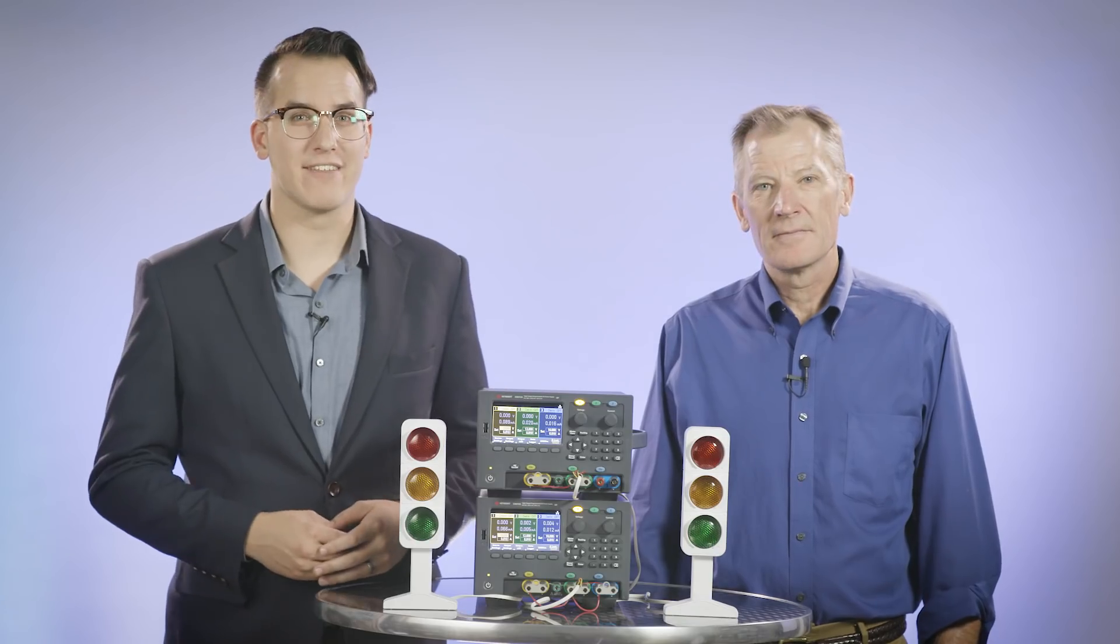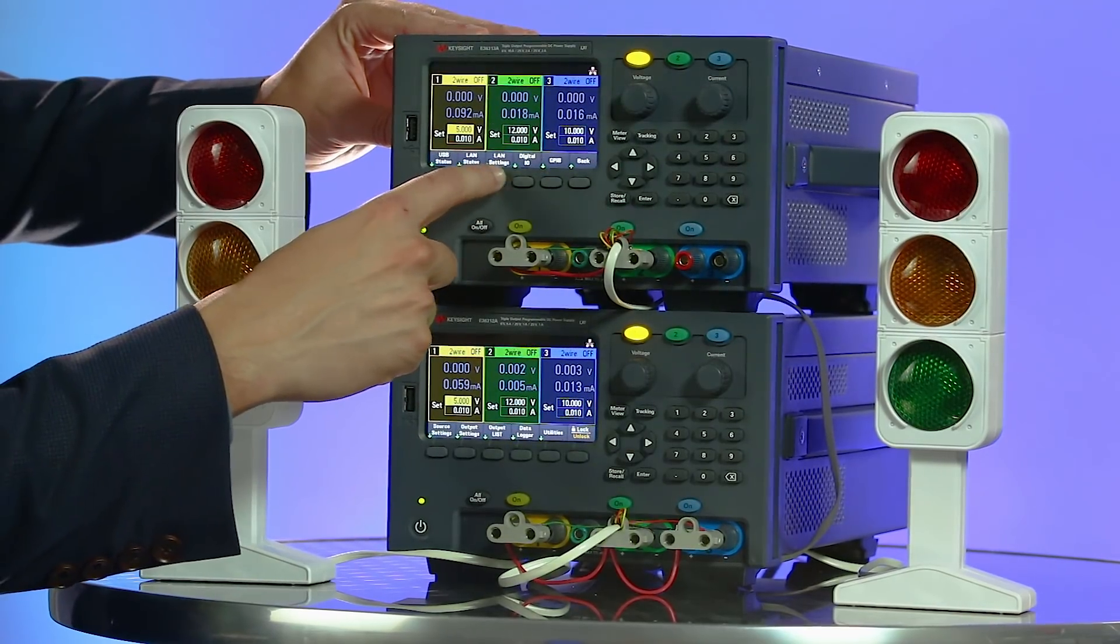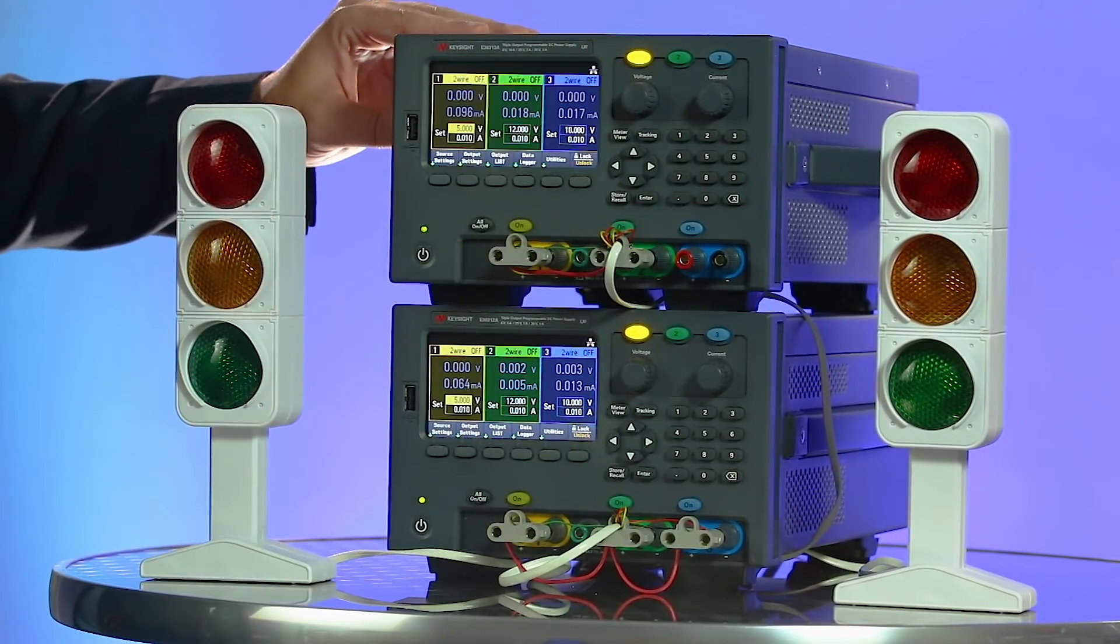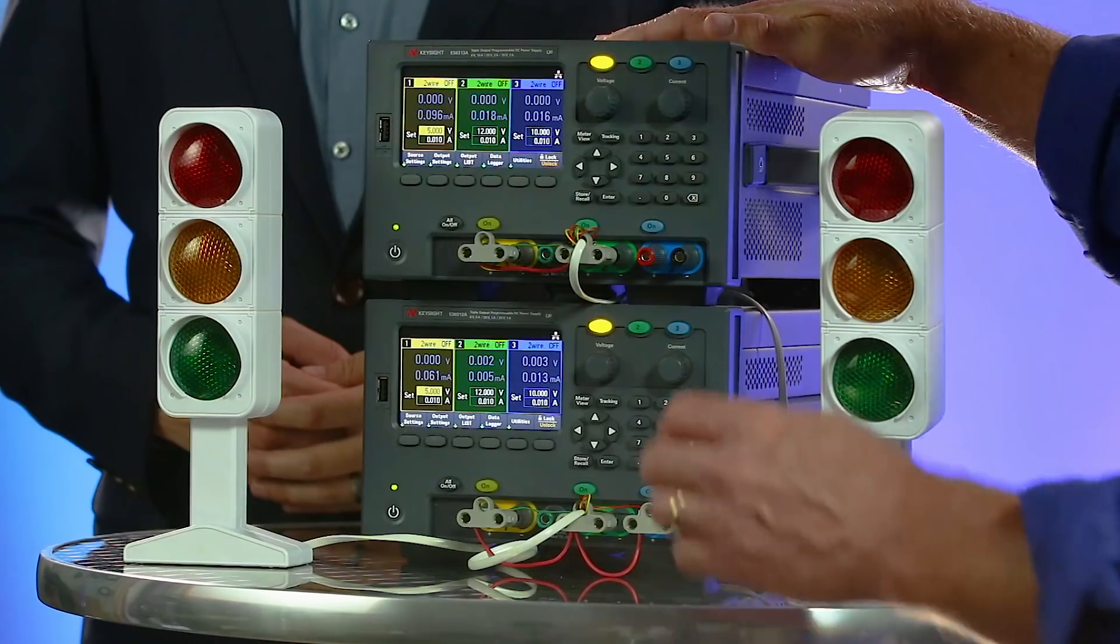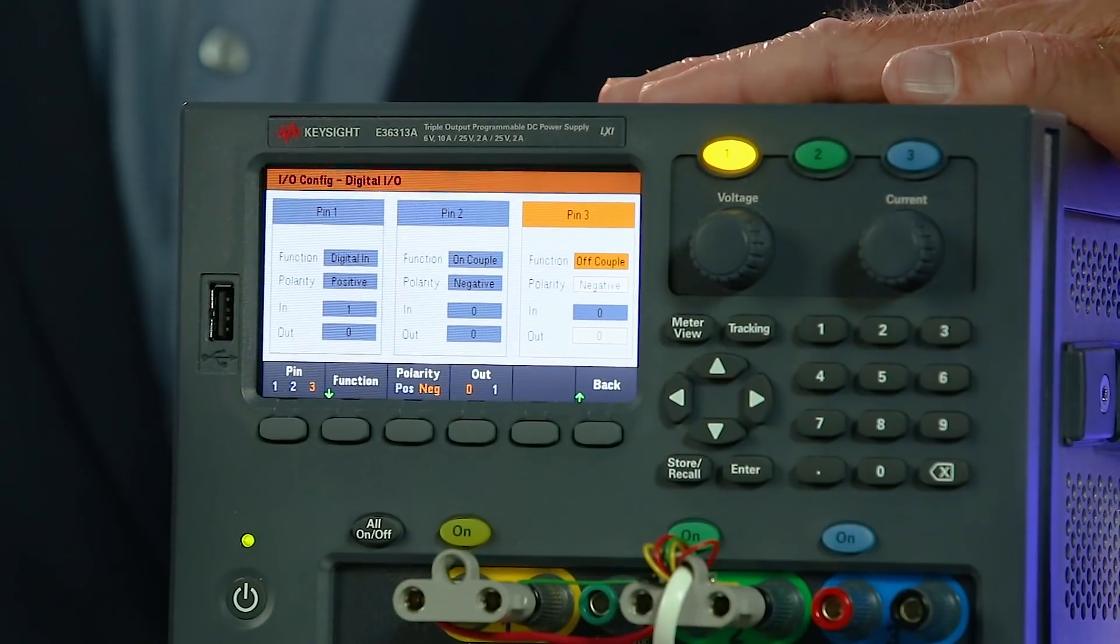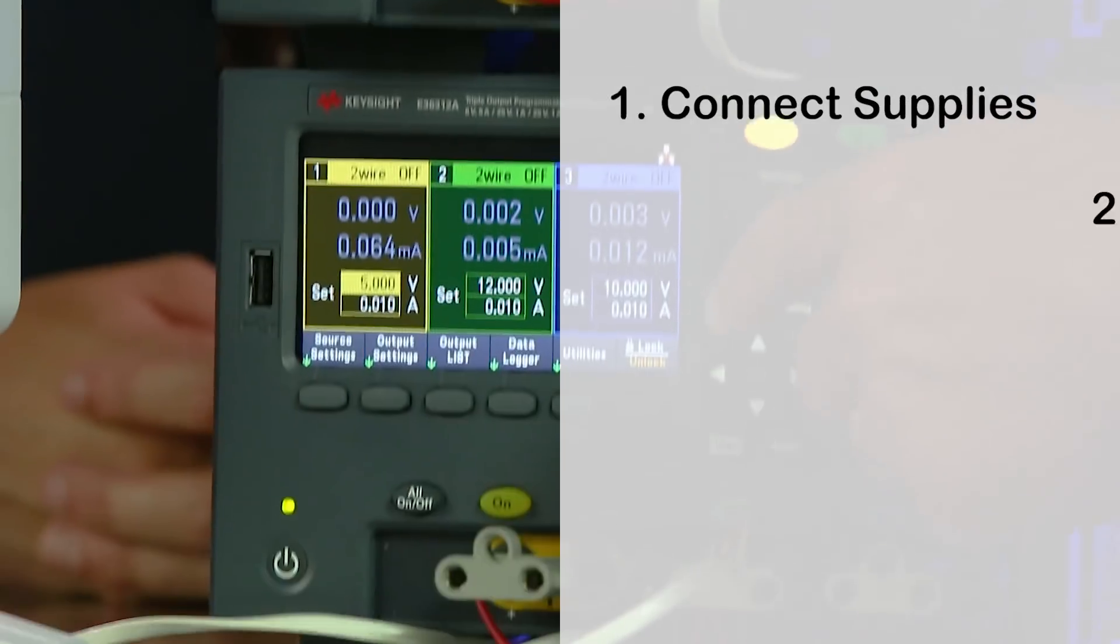A quick fun UI fact that Bill taught me, the meter view button acts as a home button and is an easy way to exit out of any menu tree. With the digital I/O configured, we will set up the coupling in the first power supply. On the second power supply, we'll select the outputs to be enabled upon receiving the signal. I've chosen two channels. We can also set the output delays from the same screen.